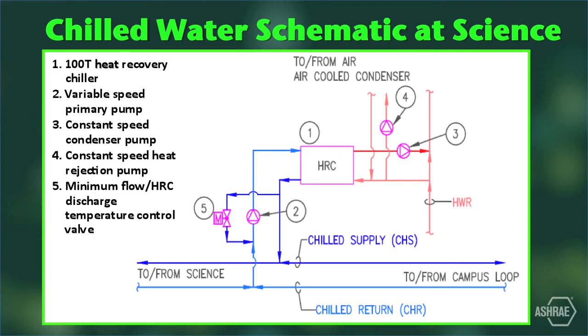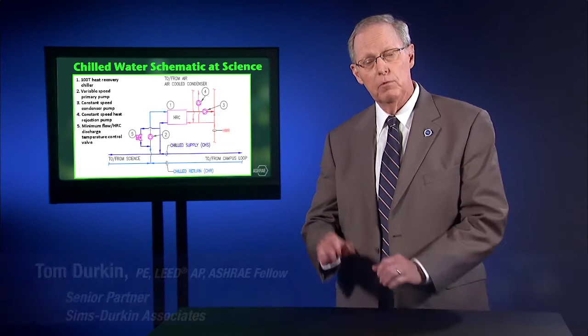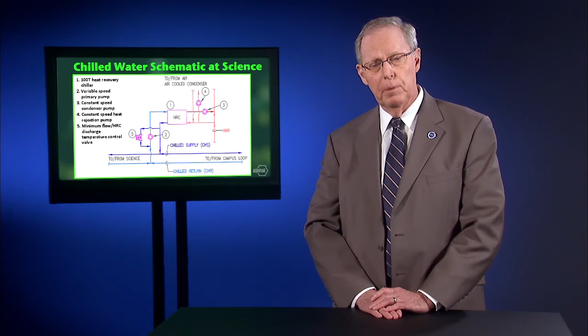This is how the new heat recovery chiller at Science Center is piped, connecting to the campus chilled water mains ahead of the science building pumps. There is an air-cooled condenser that isn't shown here. The chilled water sequences mean that the heat recovery chiller meets the chilled water requirements of the academic center. The heat recovery chiller runs to meet the summer hot water requirements for all three buildings. The heat recovery chiller runs to meet the campus chilled water requirements in wintertime, and with the air-cooled condenser, the heat recovery chiller can run for load if the campus loop is at capacity.